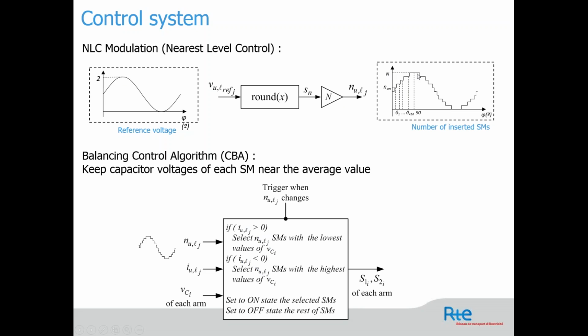The balancing control algorithm is the last control system used, and its aim is to balance each submodule of each arm. Here you need the number of inserted submodules, so it is connected to the NLC. You need to measure the current of each arm, and the capacitor voltage of each submodule. By doing a sort function, you can check which capacitor voltages are the highest, and then you can balance depending on whether the current is positive or negative.